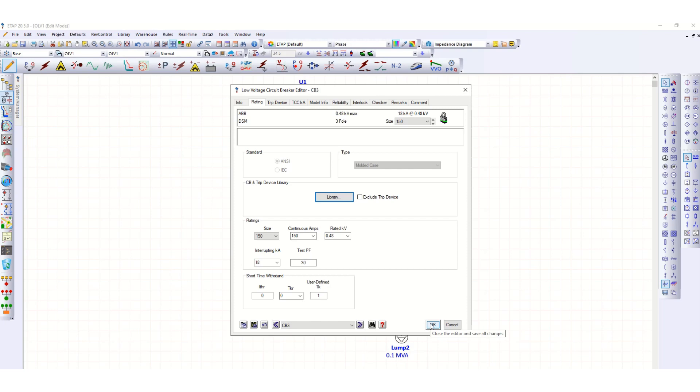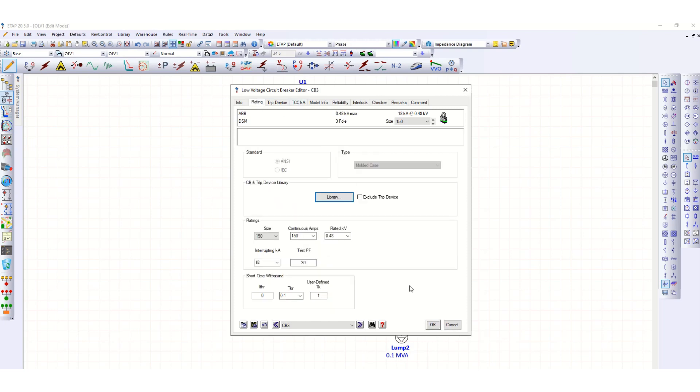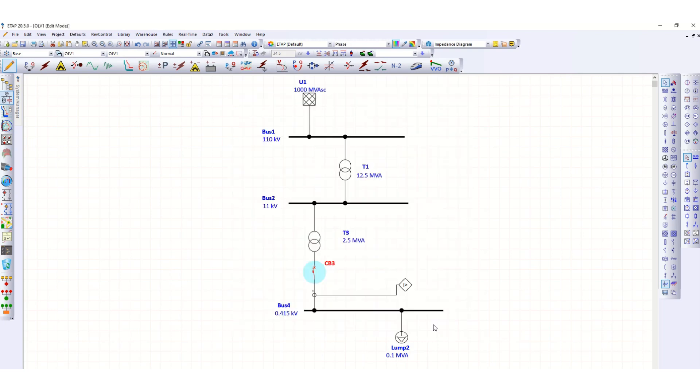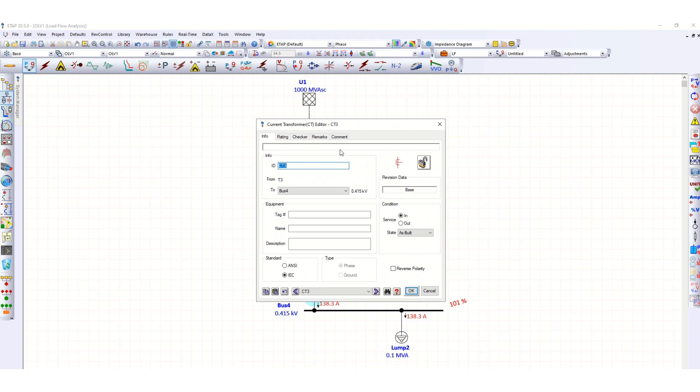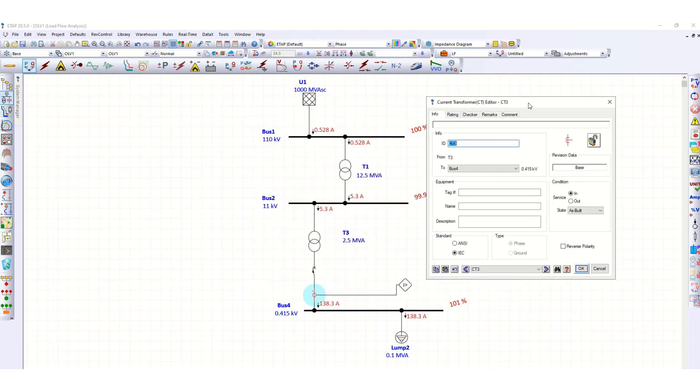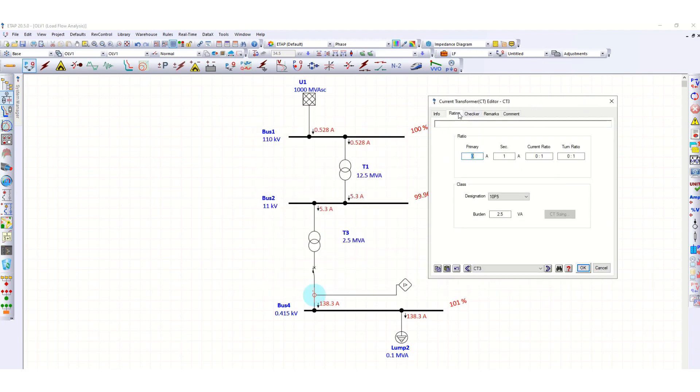To define the values, let's run the load flow once again. This was 138.3 ampere. Let's define the CT3 rating. Suppose this is 200 to 1 CT with 10 VA burden.